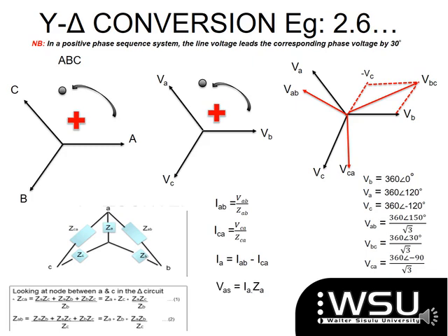And I utilize that to calculate my VAS, because now I've got a star over there, so I know that the voltage across will be VAS as is on my load side. It's no longer my VAN. So I calculate my VAS utilizing my IA that I've just worked out, and I can utilize my ZA that I had already in the given scenario. I then am able to work out my star point potential as VSN, which is going to be VAN minus my VAS.